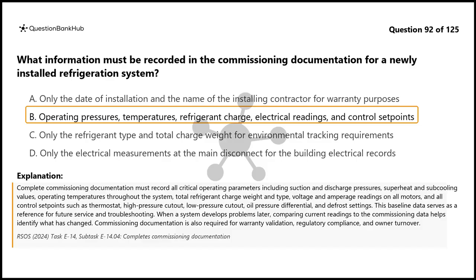This baseline data serves as a reference for future service and troubleshooting. When a system develops problems later, comparing current readings to the commissioning data helps identify what has changed. Commissioning documentation is also required for warranty validation, regulatory compliance, and owner turnover.